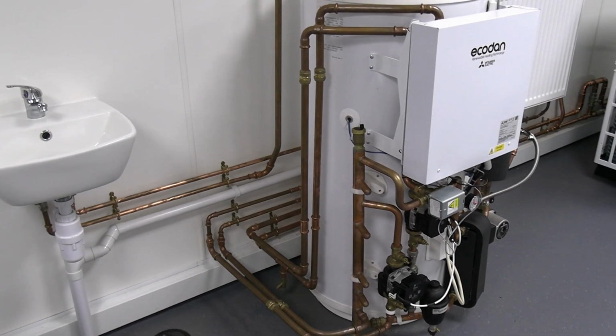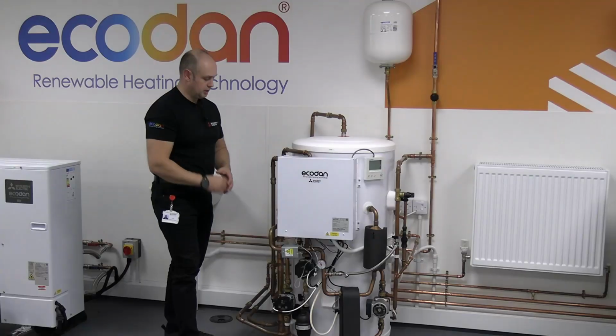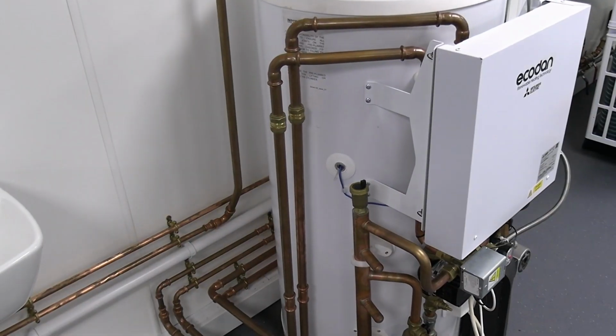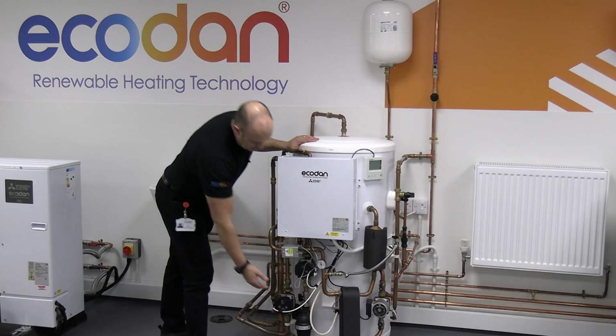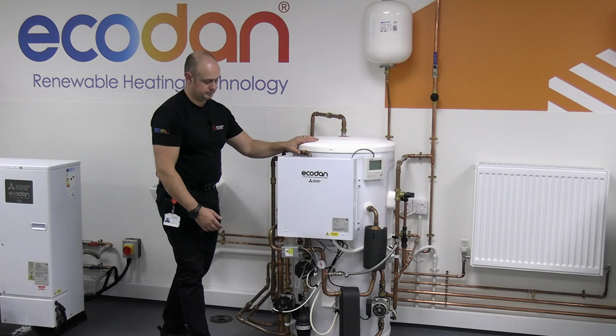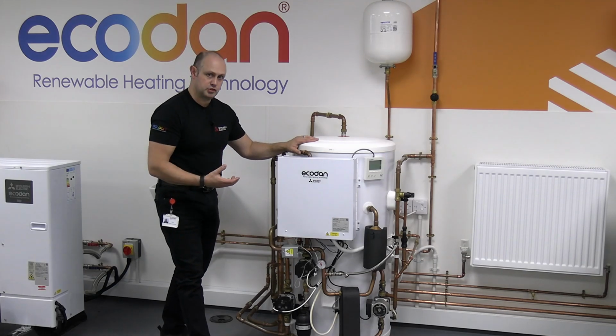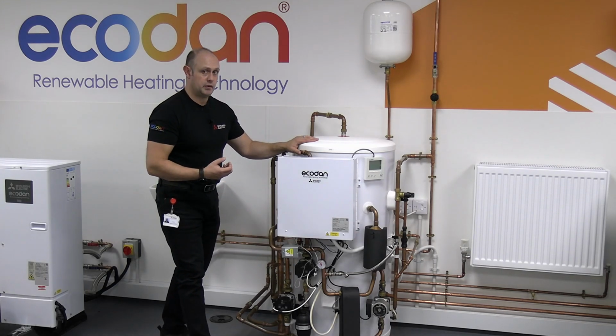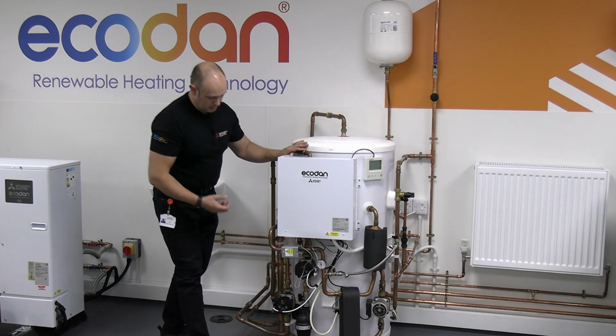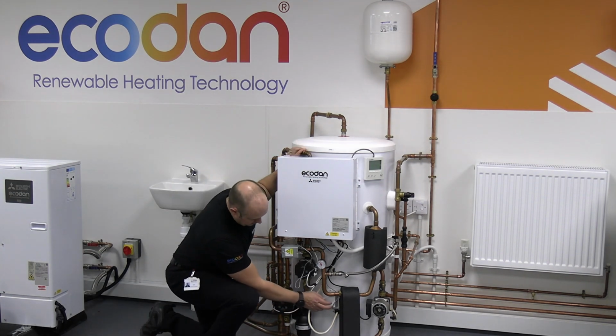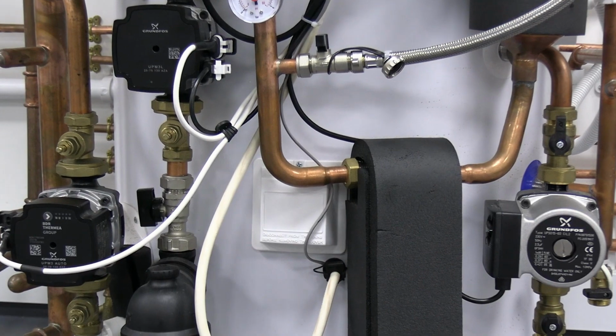On the cylinder, we've actually got 2 temperature sensing points. One about 1/3 of the way down the cylinder, and another one about 1/3 up from the bottom of the cylinder. So that's giving us better temperature control of that cylinder and a better idea of how we're heating up that cylinder. At the bottom here, we've also got an immersion heater.